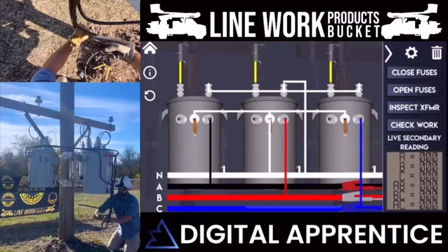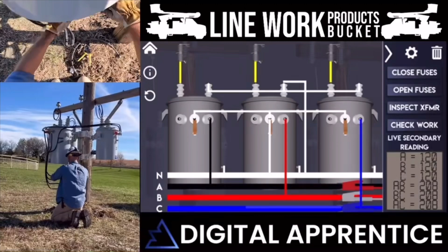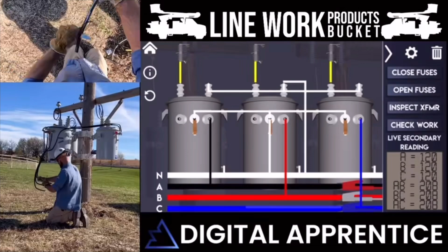But anyways, I go ahead and start cleaning up these legs, and I'll make them all the same length. Makes it look cleaner. And then you put some blocks in there, and you can add services to it. But when I get to the neutral, I'm going to skin the entire neutral bar, and it turns it into a neutral bus essentially. And you want to make all your neutral connections on that section of wire and not on the system neutral, because the more connections you have on the system neutral, the more likely it's going to burn that wire down. You don't want a bunch of wire in the backyards and stuff.